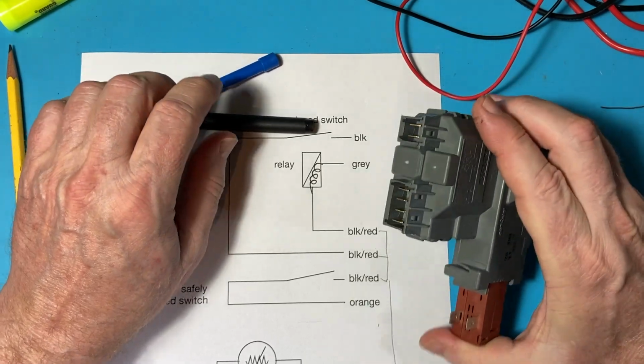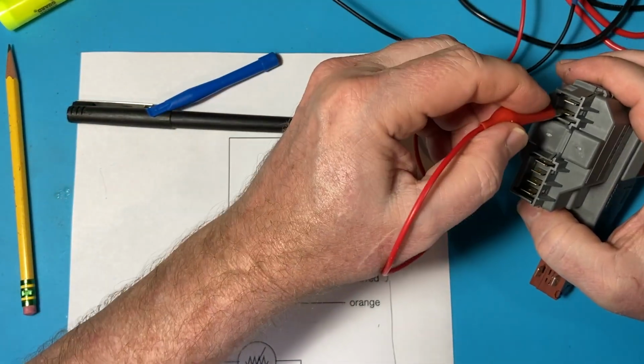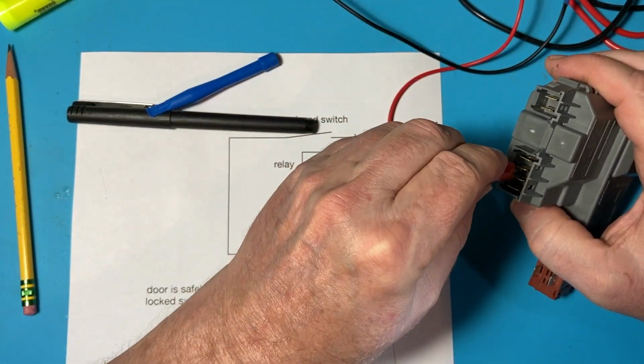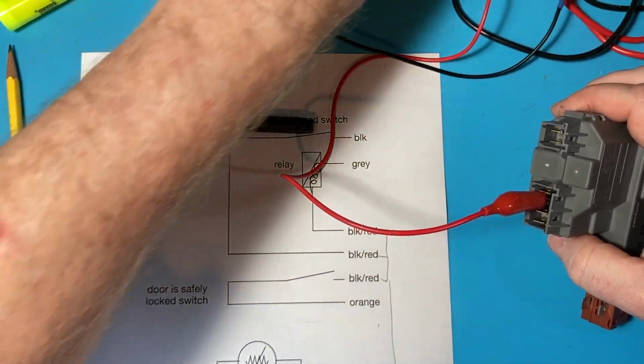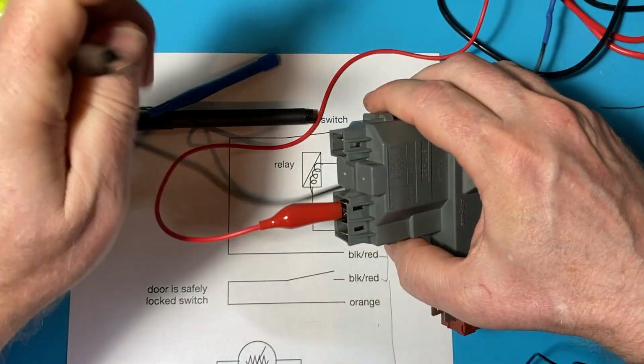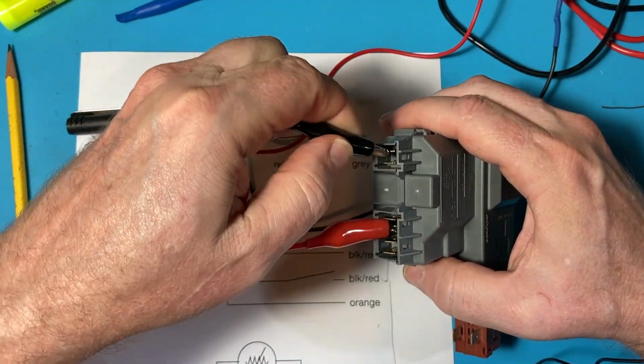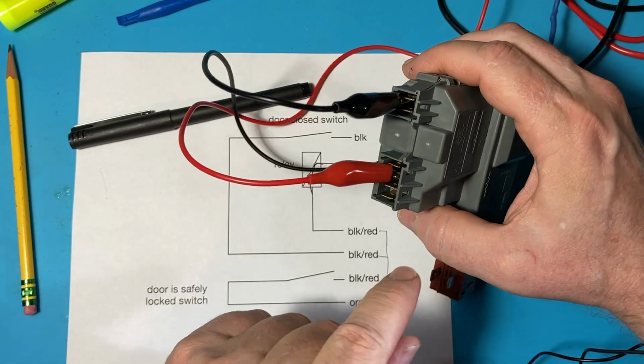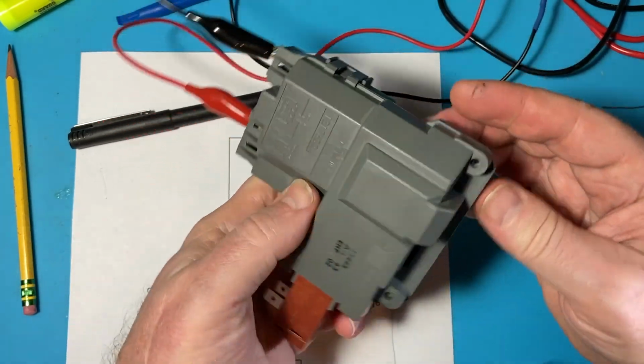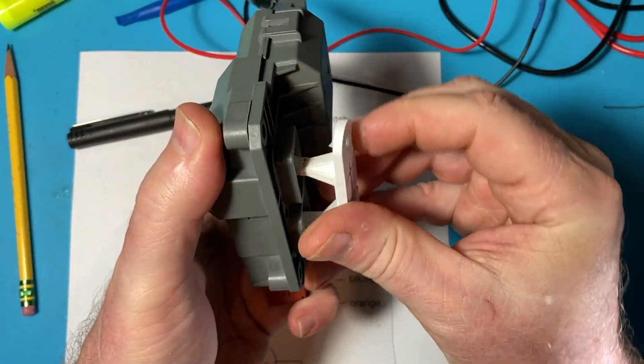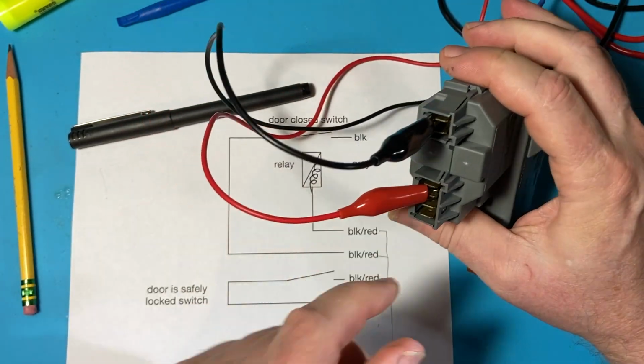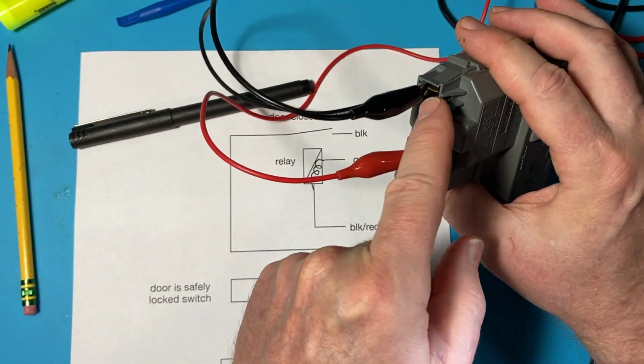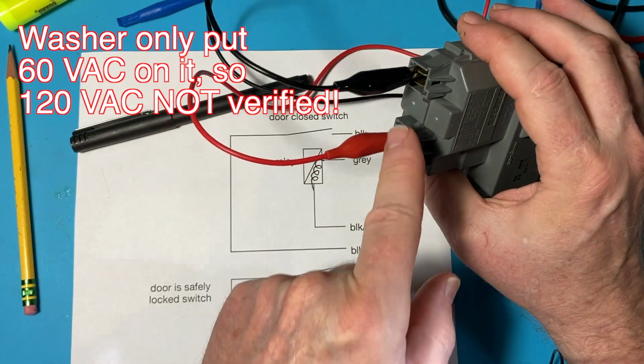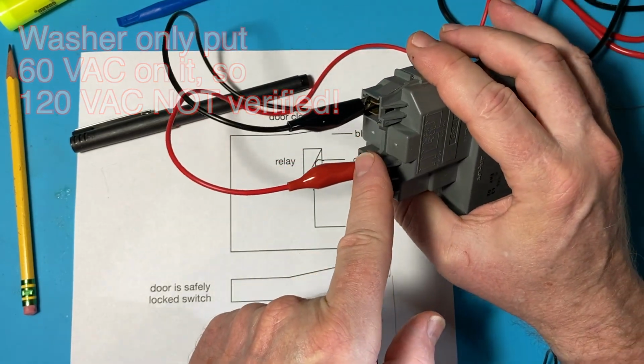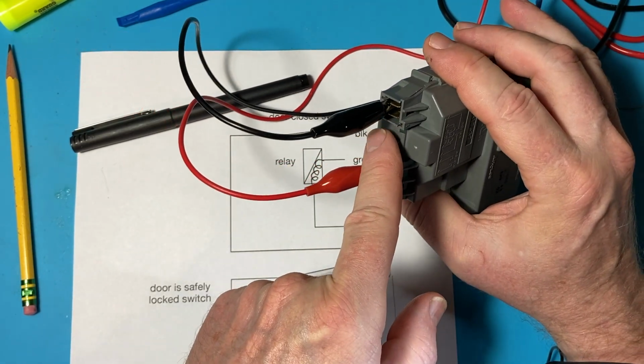So one test you could do is put the beeper on the two door closed contacts, which are these. Then insert the key into the lock, and then put 120 volts on these other ones. But I would actually make up a wiring harness with some lugs, because these are so close together and you don't want to shock yourself.